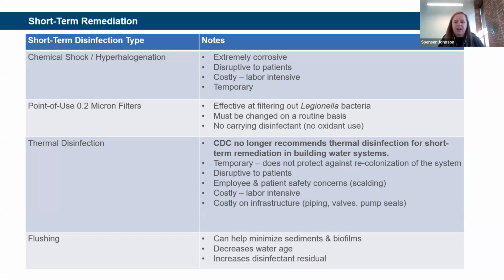Another option is a thermal disinfection. So this is when you would raise the temperature of your hot water system to kill the Legionella bacteria throughout. When the CDC released their Legionella sampling toolkit, they no longer recommend doing this as a short-term remediation because they found that the recolonization period afterwards is so quick that it's just not a recommendation. And you'll see it's pretty similar to doing a hyperchlorination. It's temporary. It can be disruptive to patients because since you have to raise that temperature so high, you can't use the water at that point. It's going to be a scalding risk. And it's also labor intensive, and it can be costly on the infrastructure. People see leaks, and plumbing seals failing at those high temperatures that they weren't meant to see.